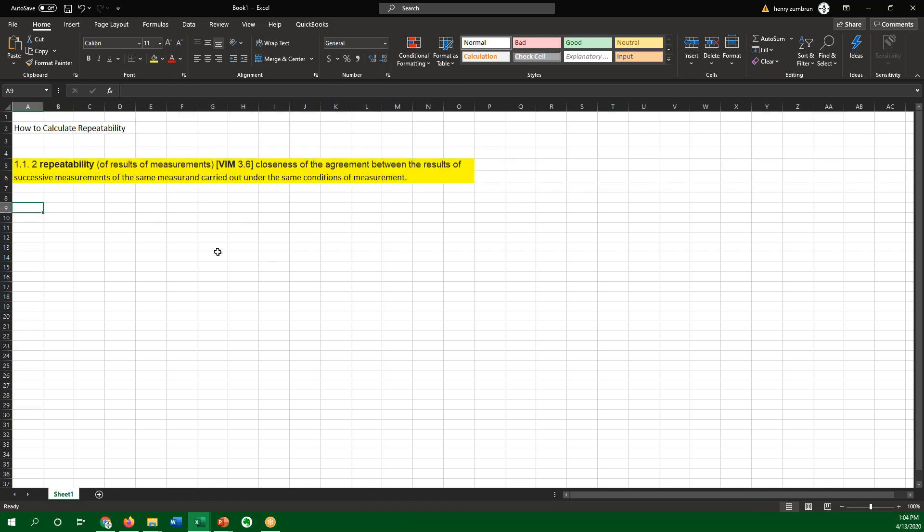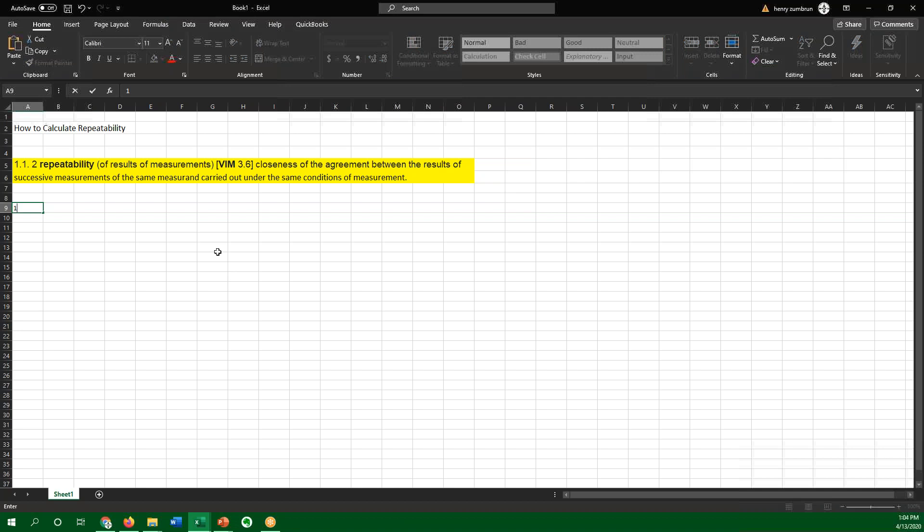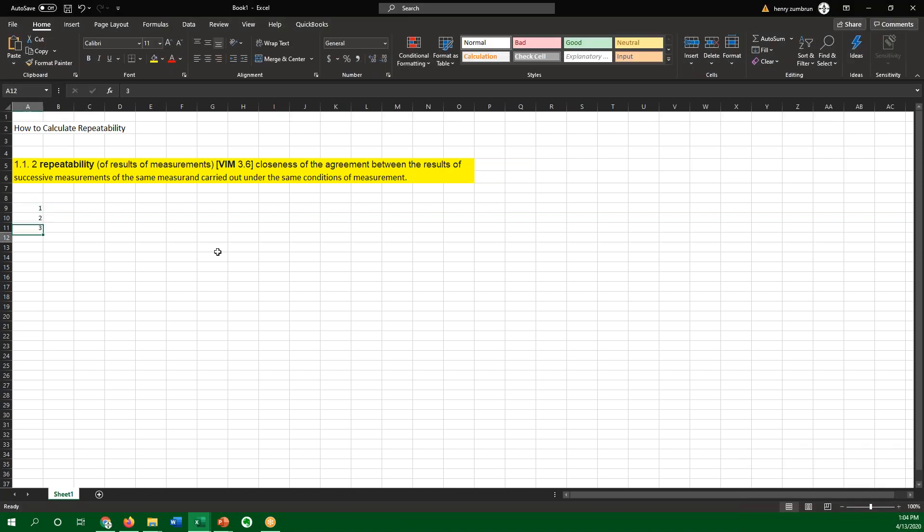So if we wanted to look at how to calculate repeatability, it's really as simple as taking the standard deviation of measurements. And if we have trials, and if we're doing a range, we may want to do it for each point in the range.